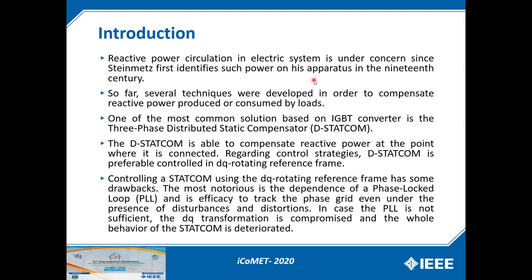One of the most common solutions is the STATCOM, which is a solution based on an IGBT converter. STATCOM means the three-phase distributed static compensator. And the STATCOM, which is a quite familiar solution, is able to compensate reactive power at the point where it is connected. And regarding the control strategy of STATCOM, the most conventional and the most preferable is the DQ rotating reference frame. So you make all your control strategy within this frame, the DQ rotating reference frame.